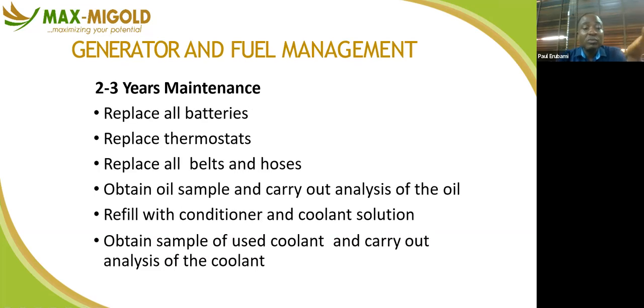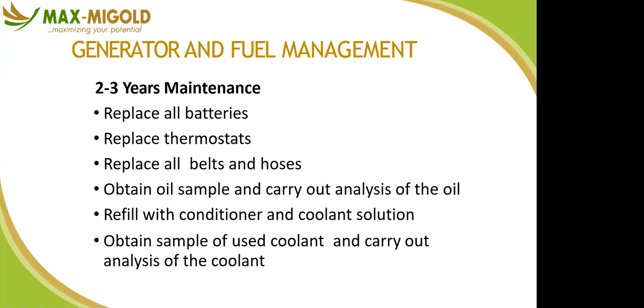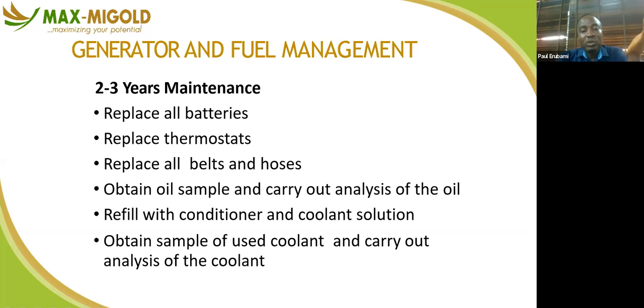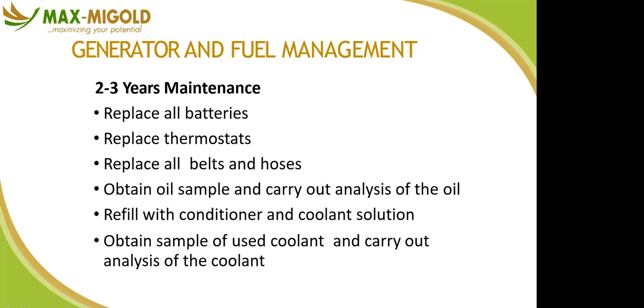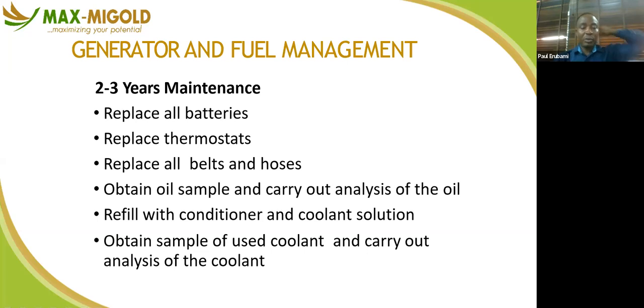And every 2 to 3 years, replace all batteries. Some batteries may last 3 years, 4 years, but at this standard, you should replace all batteries, replace the thermostat, replace all belts and hoses, because they all have their lifespan. So these are the things you do every 2 to 3 years. When you have adequate records, it is easier to do this. That's why it's good to keep a record of what you do on site.